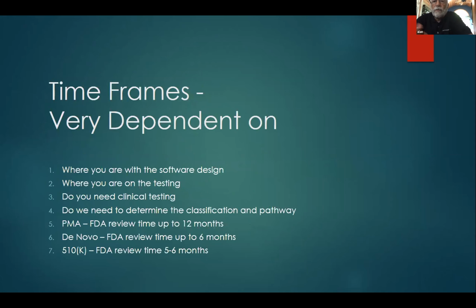Timeframes. Now, timeframes on getting the product through the FDA are very dependent on where you are with the software design. Everybody wants to know how fast we could get these products through the FDA. Where are you on your testing? Do you need clinical testing? Do you need to determine the classification and the pathway? PMA, FDA review could take up to 12 months. De novo, 6 months. And 510K, 5 to 6 months, maybe 3 to 5 months. So the pathways and the time are very related to each other.